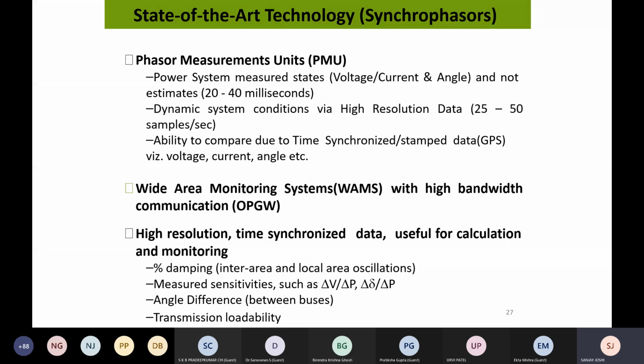WAMs with high bandwidth communication is a technology which is employed in present day. High resolution time synchronized data is useful for calculation and monitoring of the following parameters: percentage damping, inter area and local area oscillations, which were not possible in the previous case where the measurements from SCADA were used. Measured sensitivities such as delta V by delta P, delta theta by delta P. So that is possible to measure using WAMs and PMUs. Angle difference between the buses.